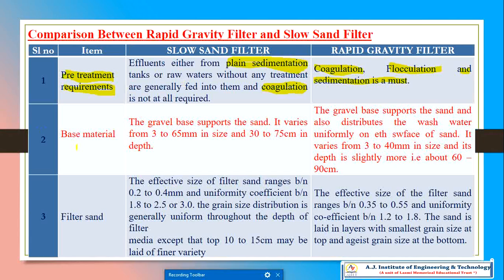Now we will go to another item — that is base material. The base material is gravel. This gravel-based support holds the sand. The size varies from 3 to 65 mm, and the depth is 30 to 75 centimeters.